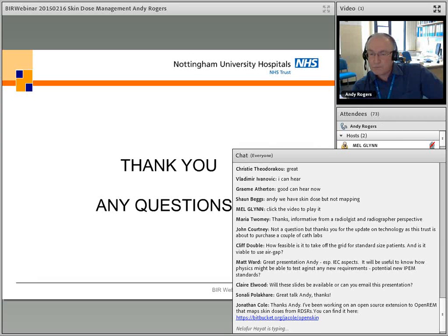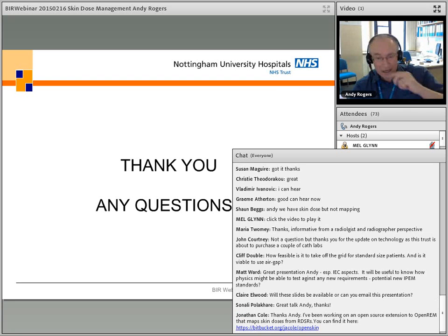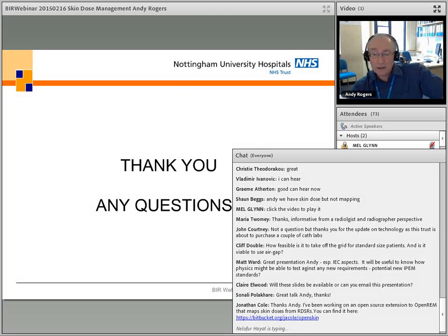Okay, I got a question from Matt. Useful to know how physics might be able to test against any new requirements. Potential new IPEM standards. Well, anyone from IPEM out there? I'd say if we want a new IPEM standard, they should have already started about 20 years ago. Things seem to take quite a long time coming out of IPEM. However, what I would say is if we can get the NEMA standard XR27 implemented on equipment, be it through the IEC route or not, that'll give physics ways of testing equipment because it'll give you a physics mode and also it gives you the images before they've been processed. So they're for presentation images. So I think that's really good.